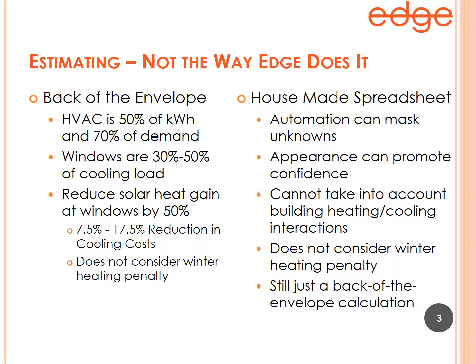For example, your HVAC is 50 to 70% of your consumption and 70% of your demand. Another rule of thumb is that your windows account for 30 to 50% of your cooling load. Consider that alongside a window film specification that reduces solar heat gain by 50%, and you can start extrapolating: 50% × 30% × 50% on the low end, or 70% × 50% × 50% on the high end.